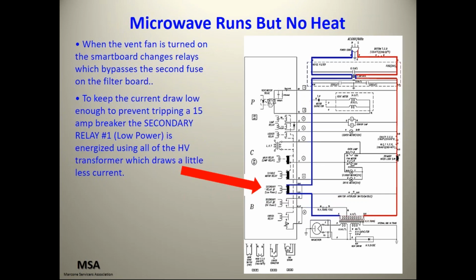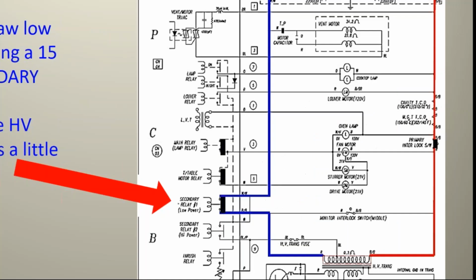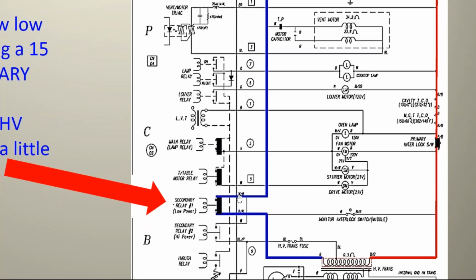When the vent fan is turned on, the smart board changes relays, which bypasses the second fuse on the filter board. And again, try that. So the smart board, the power board, whatever you want to call it, is switching relays now. It's going through the secondary relay, which is powering the transformer, the whole primary. It's bypassing that fuse.